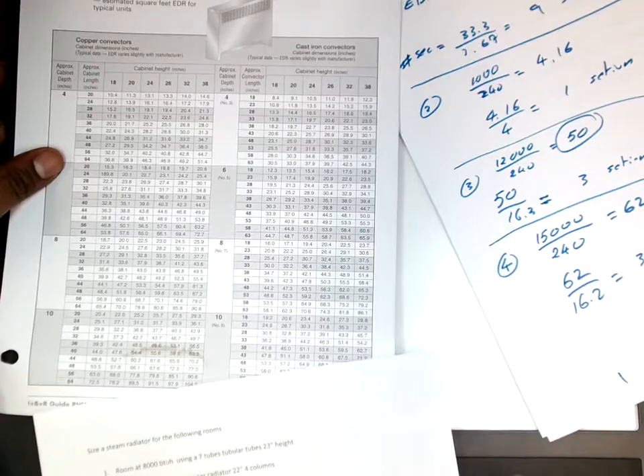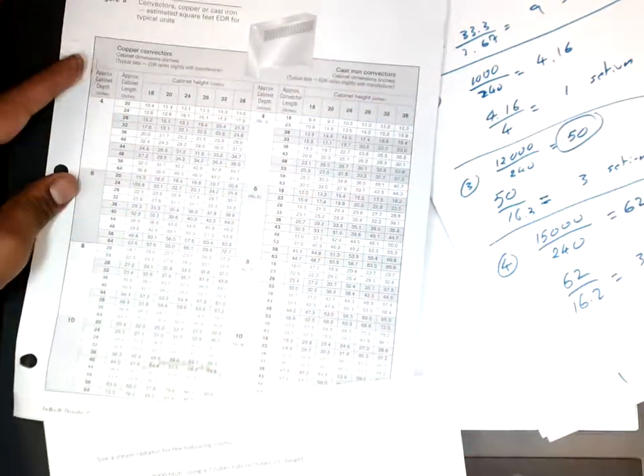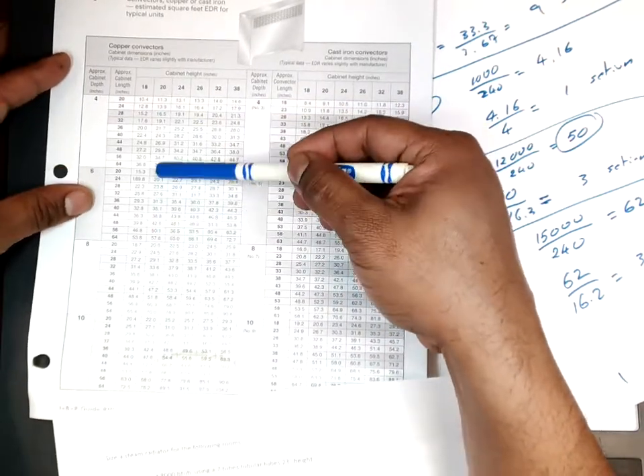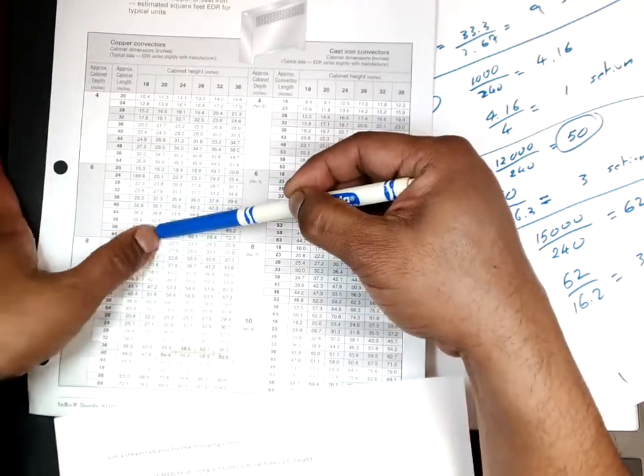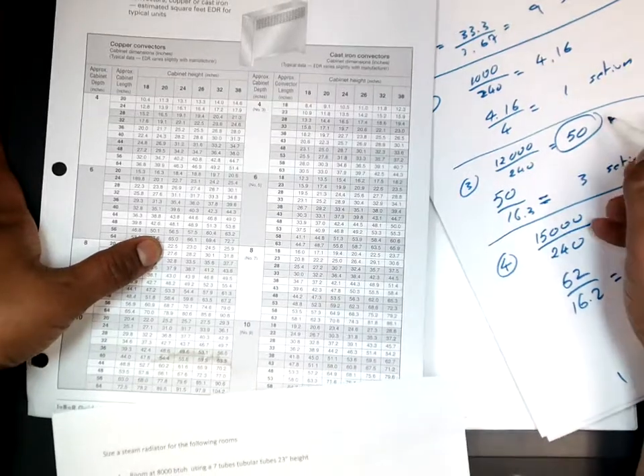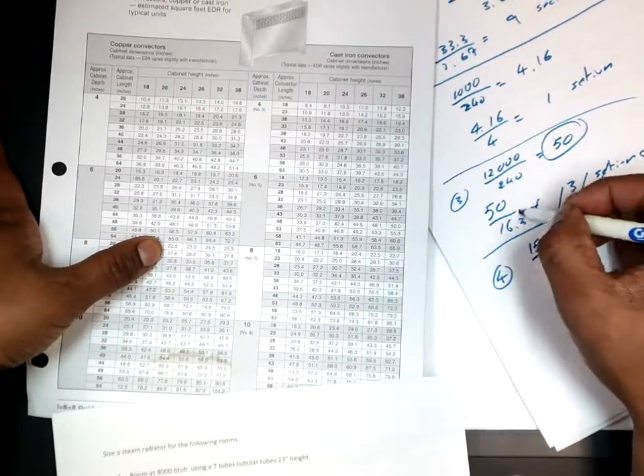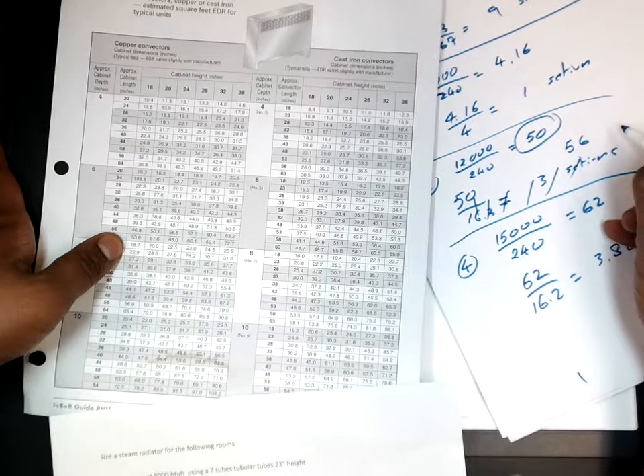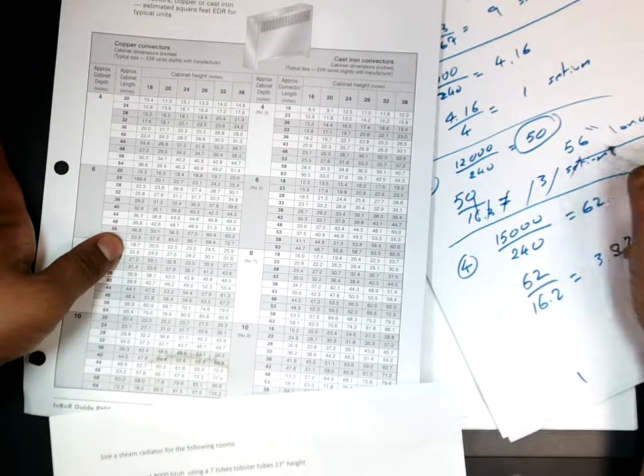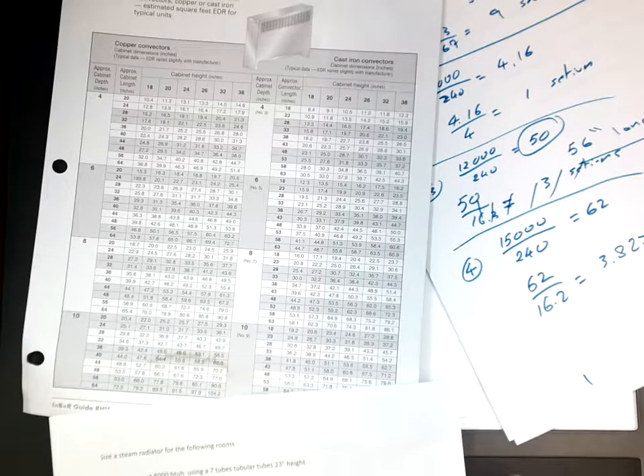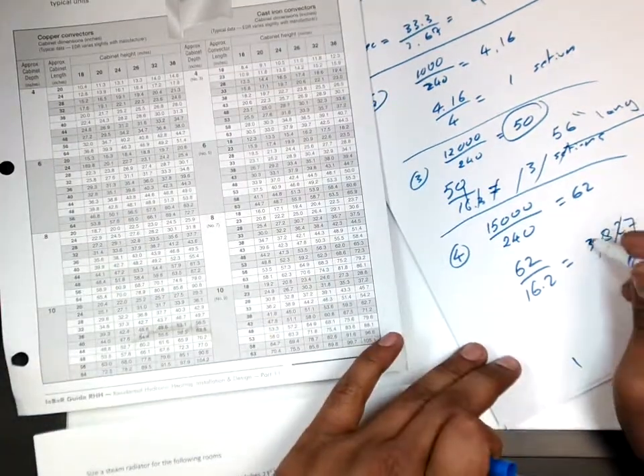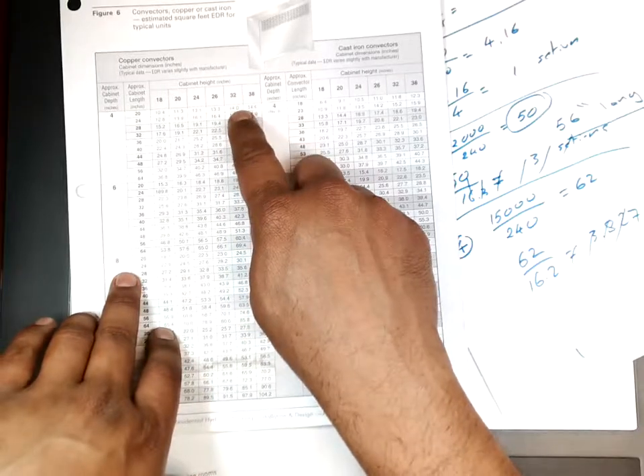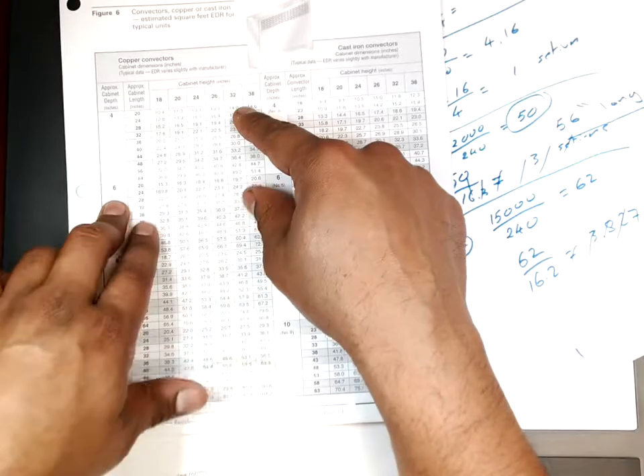So going back to question three. If I need 50 with these dimensions, 20 inches and 6 inches deep, I'm going to go and try to match these numbers here. So the closer I can get to is 50 here. So I'm sizing based on the length. So 50. I match the length. It's going to be 56 inches long. Not really? Yeah. And here, so what we do here, we have the, I gave you the length, I mean the height, and the width, and you try to match whatever length will give you the same EDR.